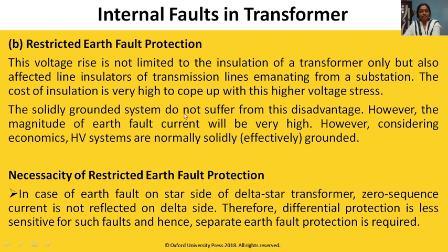The solidly grounded system does not suffer from this disadvantage. However, the magnitude of earth fault current will be very high. However, considering economics, high voltage systems are normally solidly grounded. What is the necessity of this earth fault protection?